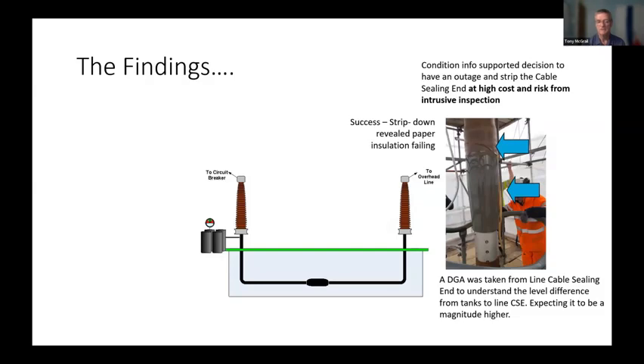So just to make sure, we took a sample from the line cable sealing end, because if the DGA at the circuit breaker end was high, we would expect it to be similarly high at the overhead line end, as it then migrates across and diffuses through the oil in the cable to the oil containment tanks on the side.